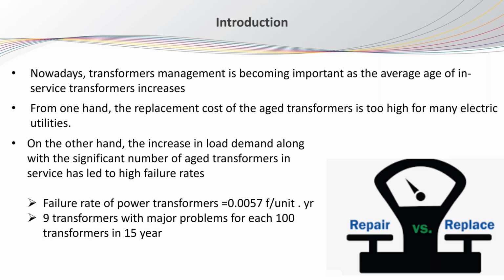According to the most recent CIGRE survey that was carried out in 2008, they found out that the failure rate of the substation transformers is around 0.0057 failure per unit year. And this means that if you have a fleet of 100 transformers, you will probably have around 9 transformers with major problems within 15 years. So this means more or less 9% of your fleet will have major problems.